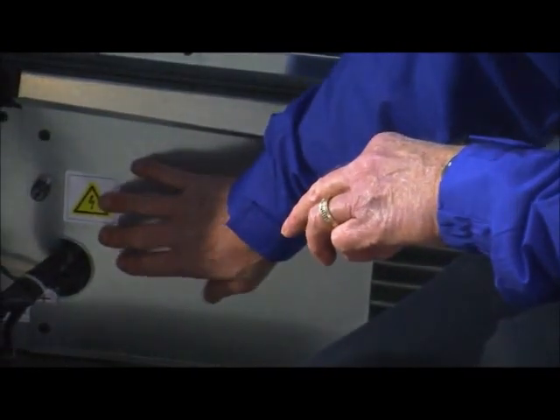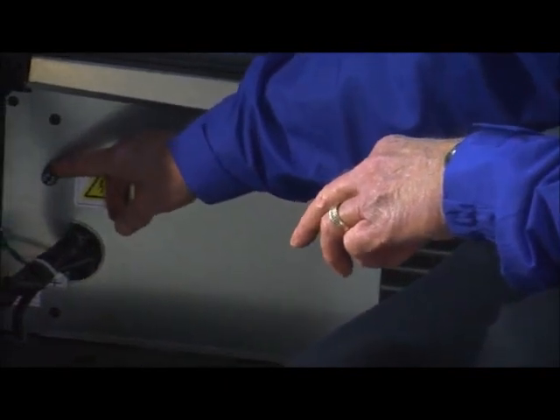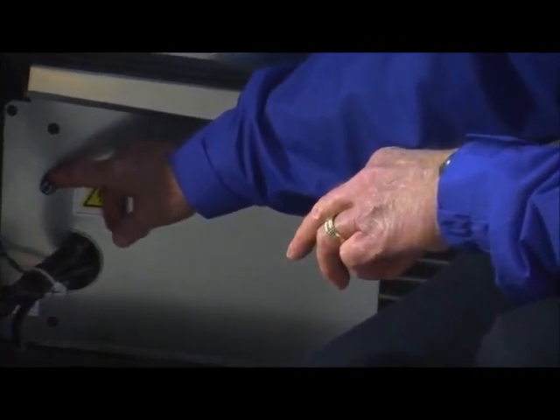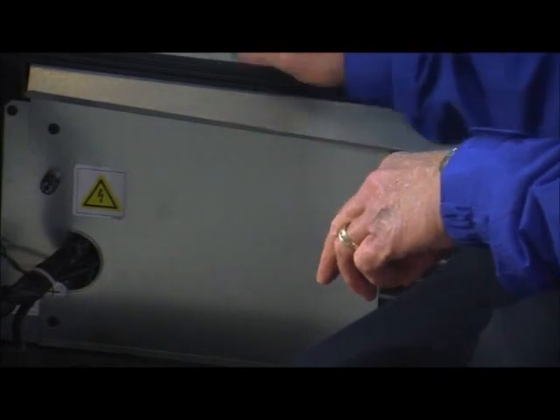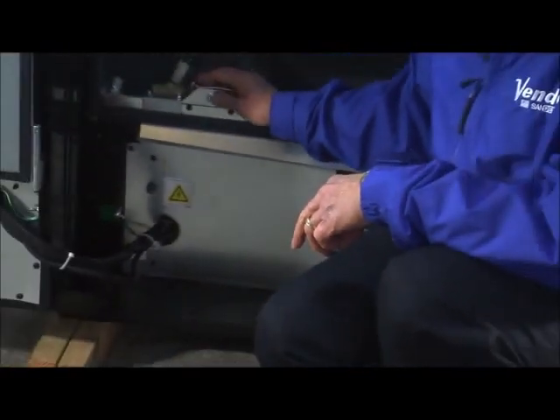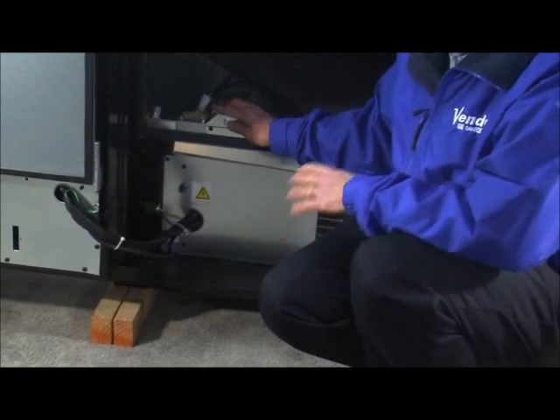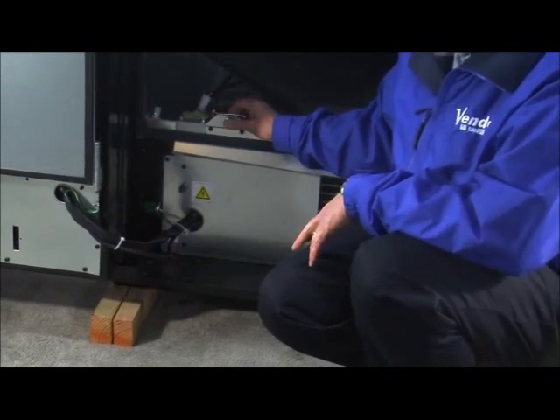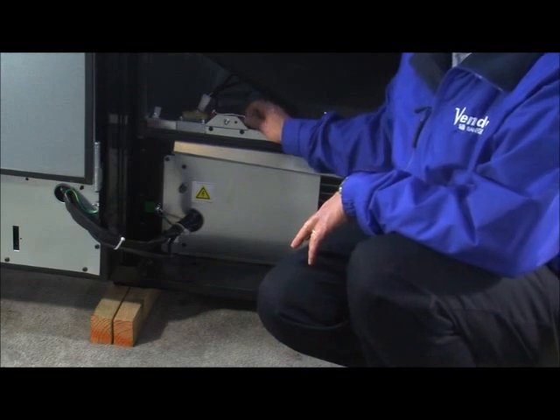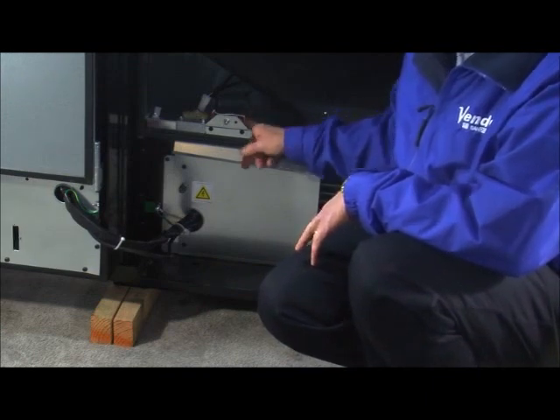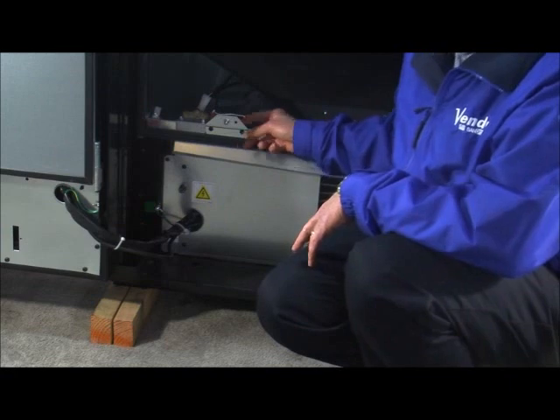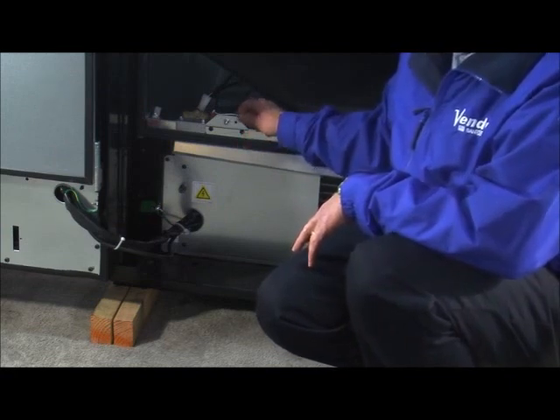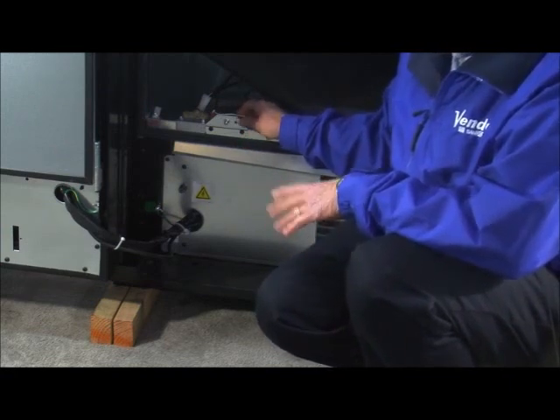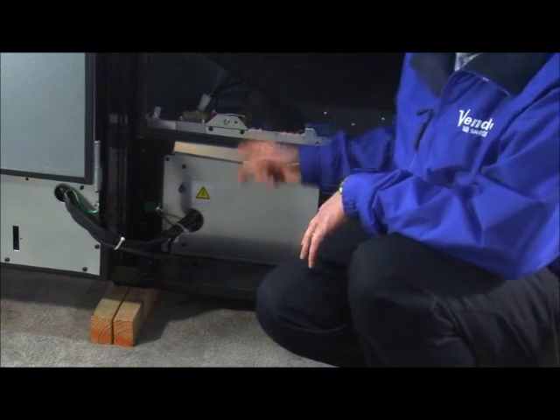Behind here, you have 3 relays, 1 for the lights, 1 for the compressor, and 1 for the evaporator. You also have a 0.8 slow blow fuse right here that's in the 24-volt circuit. If you need to check your compressor or your lights or the relay, you can do so by pushing the door switch in, or you can pull the wire on the right hand side here, the front pole, and that will allow the door switch to turn the lights and the compressor on. Always remember to replace your wire.